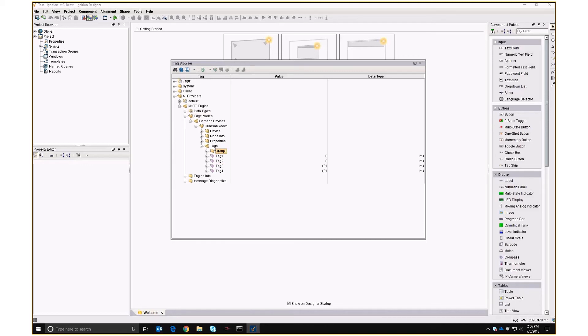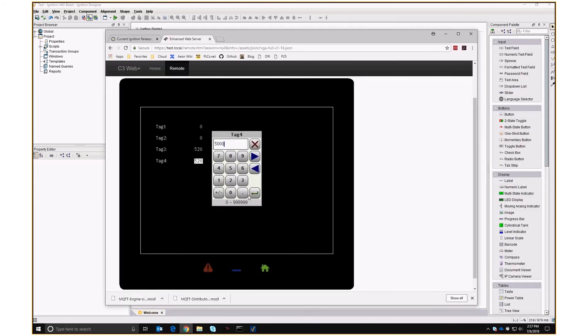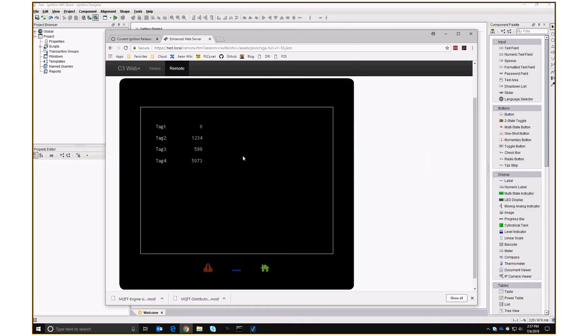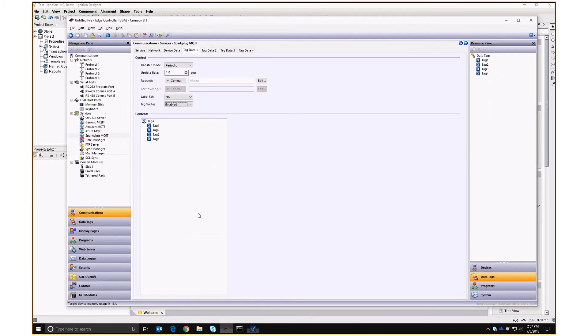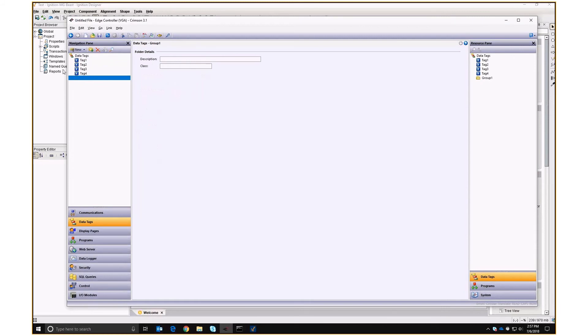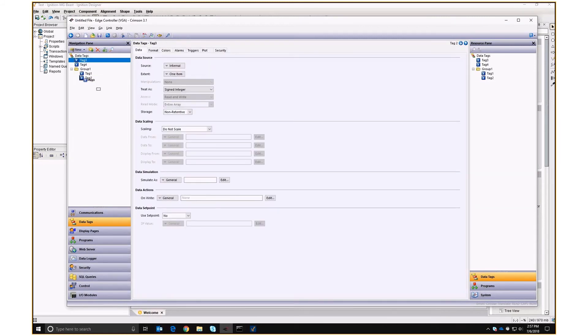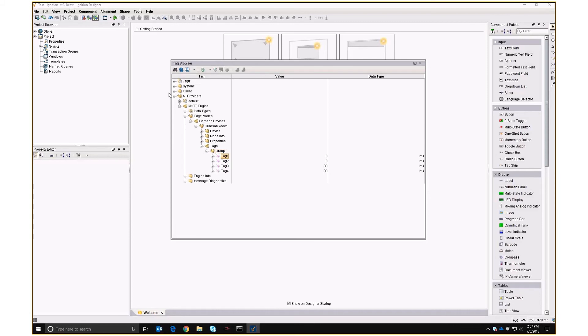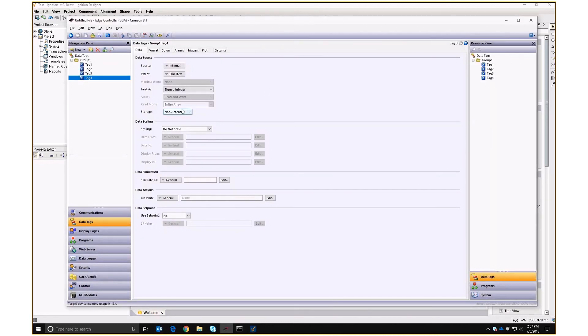Those are the four tags coming across and they are updating. If I go into my web browser and set one to 5,000, and come back in — sure enough it's 5,000. Setting values like 1, 2, 3, 4 prompts that rewrite mode is needed, which I did enable — and there it is. A nice feature is that if we have a hierarchy of tags in our system and bring those across, then delete and recreate the node, the tags are organized exactly as they are in your tag structure. It works with strings, floating point numbers, and integers — it just essentially works.